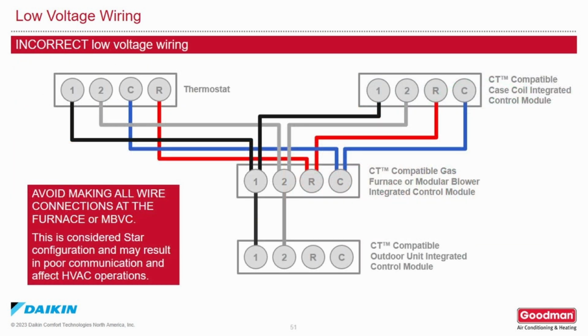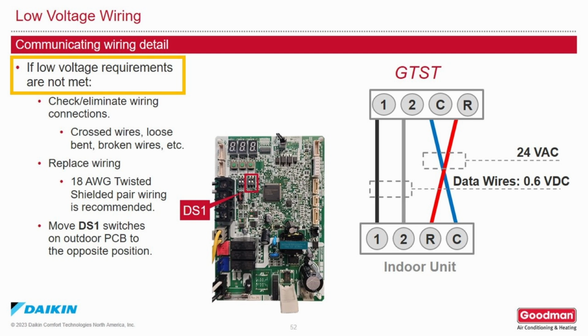Here's an example of incorrect communication wiring. Remember, communication is a daisy chain. Outdoor unit to the furnace, to the coil, to the thermostat. Do not create a landing point for multiple connections. If low voltage wire requirements are not met, check the wiring connections for cross wires, loose wires, broken wires, bent wires, etc. Replacing the communication wiring terminals 1 and 2 with 18 gauge 2-conductor stranded shielded wire is recommended. Move dip switch 1 on the outdoor unit circuit board to the opposite position.